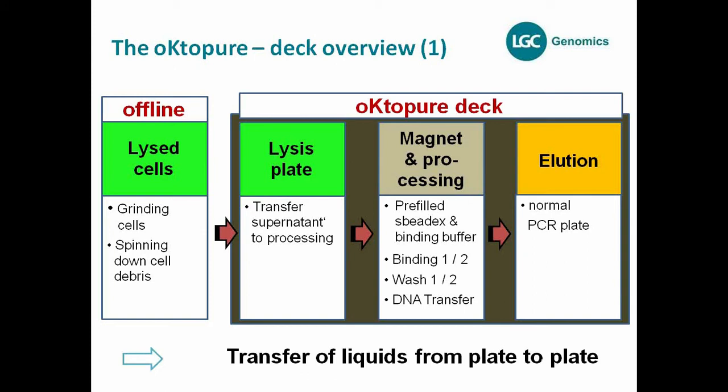Once done, you can go directly on the oKtopure — you just put your lysis plate on the deck and the oKtopure transfers 100 or 200 microliters of supernatant to the processing position, which is the magnet and processing position shown here. The complete extraction process — including binding and washing — happens here. At the end, you transfer the ready-to-go DNA to a new plate, normally a PCR plate, which can be used for further experiments like genotyping, sequencing, or whatever you're looking for.